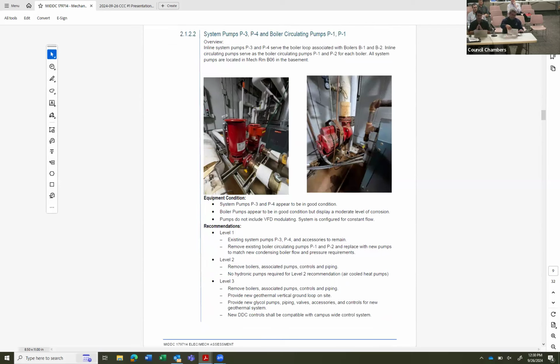The existing boilers do have primary pumps associated with each boiler that are, again, past their expected service life, but are still functioning. You can see there is some corrosion started, so those might need replacement in the near future. So with option one, we'd recommend replacing those pumps with the new boilers. But we could keep on the left here the system pumps, which are newer and would still be appropriate for the system at level one.